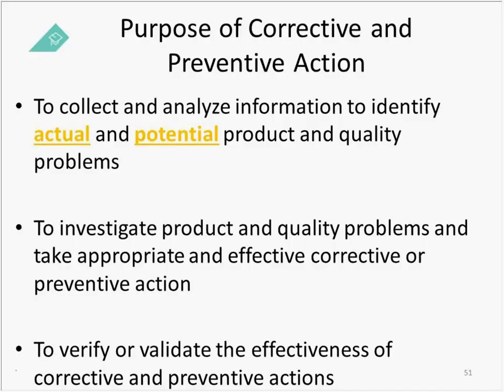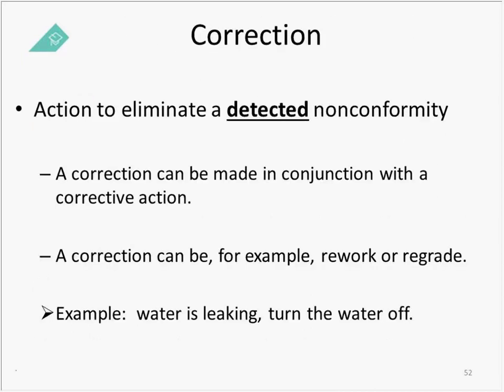The entire purpose of a corrective or preventative action (CAPA) is to identify actual and potential product and quality problems. Through investigation of your quality problems, you want to take appropriate actions to effectively correct and prevent the failure from occurring in the future. The key to an effective CAPA is making sure your corrective actions are assessed from a defined point — not just putting in corrective actions without reassessing whether they actually addressed your issue.